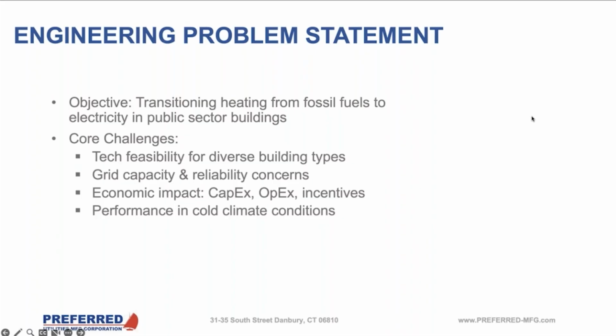Heat pumps now, most of them from major manufacturers, will go down to 0 or even -10 degrees. But their capacity starts to drop off—meaning the amount of heat they can actually put out into your system. So from 30 degrees ambient, if you go down to say 10 degrees ambient, you have a drop off of about 50% capacity.